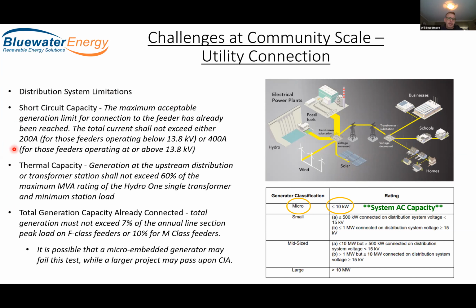Short circuit capacity is the maximum acceptable generation limit that can be connected to a feeder, and it's limited to either 200 or 400 amps based on the voltage of the feeder. Thermal capacity is the impact of generation hitting the transformer station or a substation somewhere along the distribution system, and shall not exceed 60% maximum of the total volt amp rating at the transformer. And then total generation capacity, interestingly, for micro generation, which is what we're talking about, 10 kilowatts or less, typically for residential projects, because of the costs of going above that, which I'll show you here in a minute.